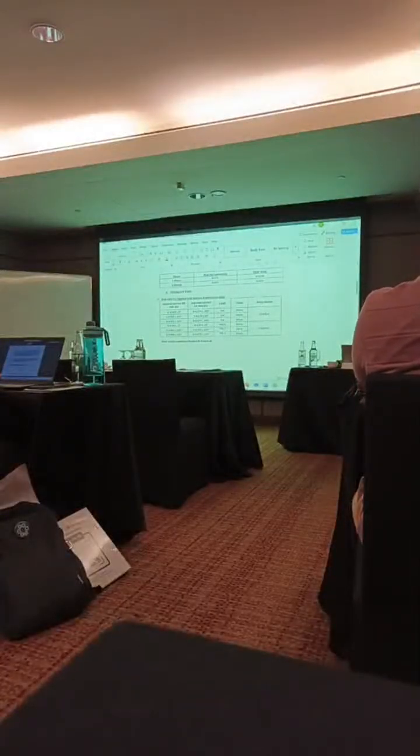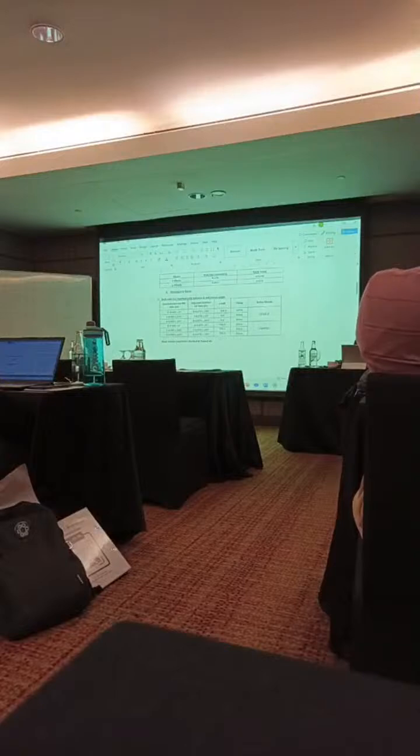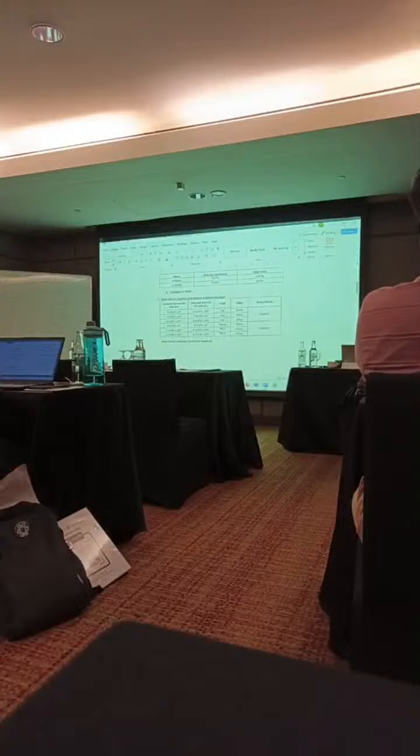So this is the stable condition. You can see in the stable condition, the differential current will be almost zero. It is 0.8 ampere, not per unit.